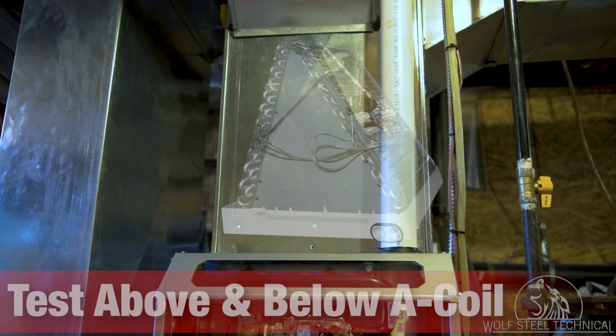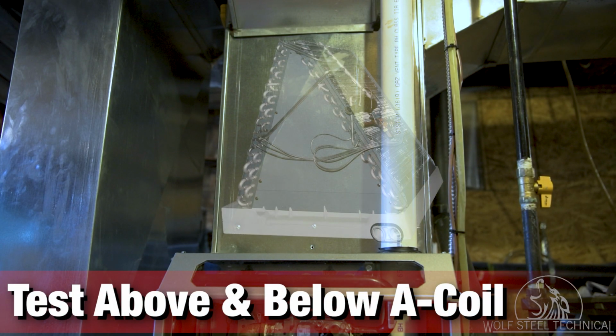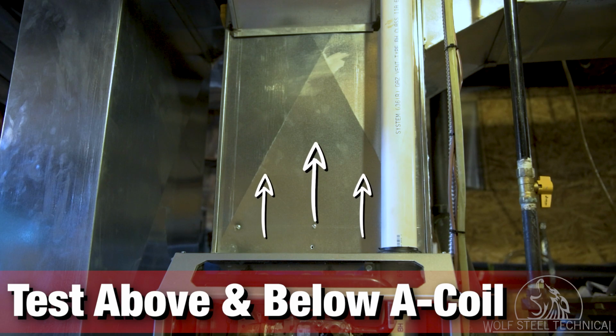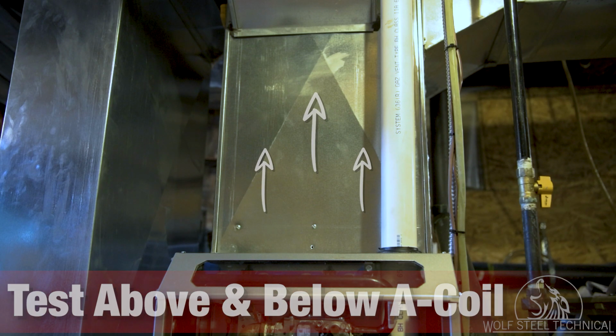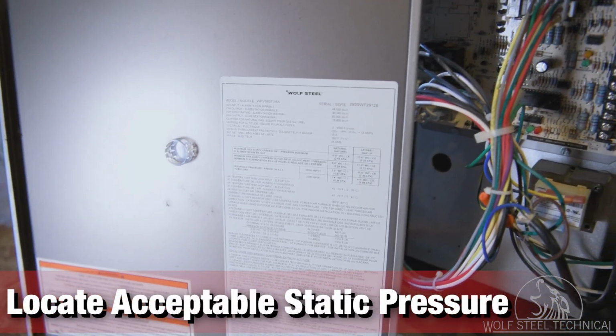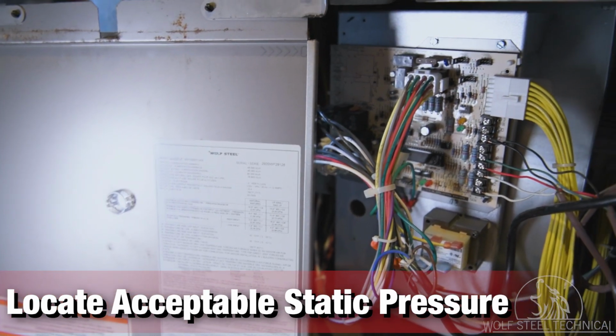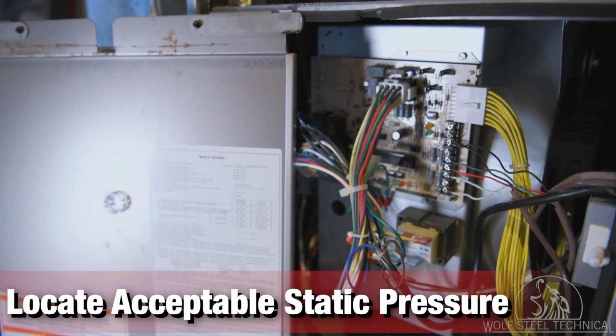When the system contains an A-coil, calculate the static pressure both above and below the coil to identify the difference in pressure at both these locations. This will allow you to identify if the coil is dirty, which would cause a significant strain in the system's operation. To locate the acceptable static pressure range for the specific appliance, refer to the product's installation manual or the rating plate.